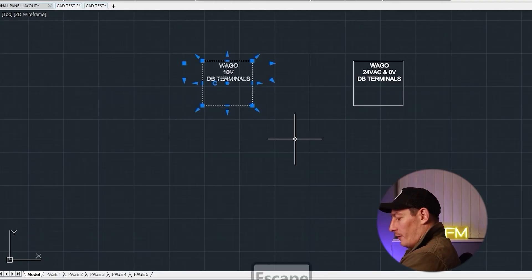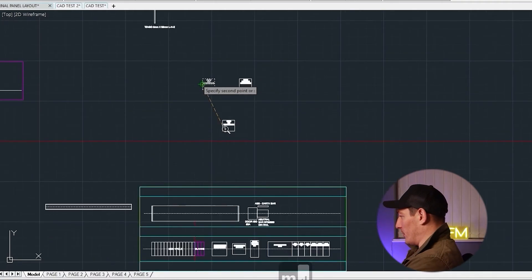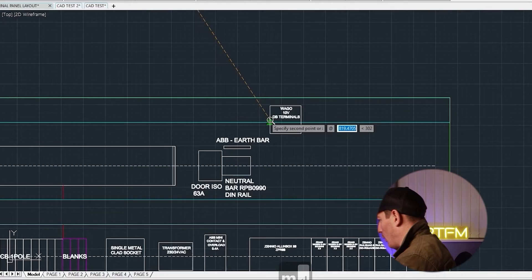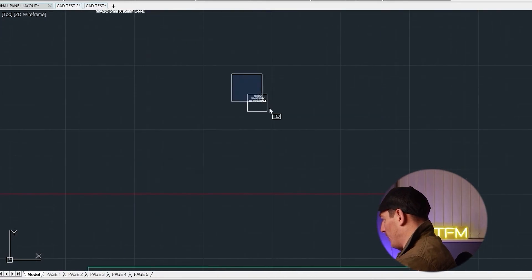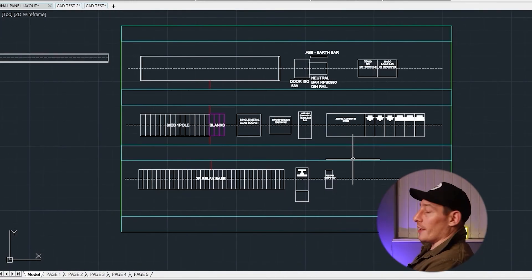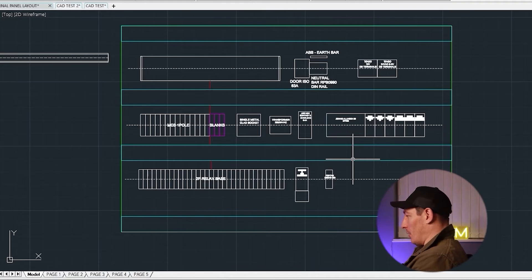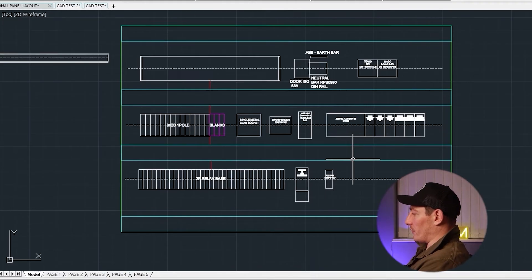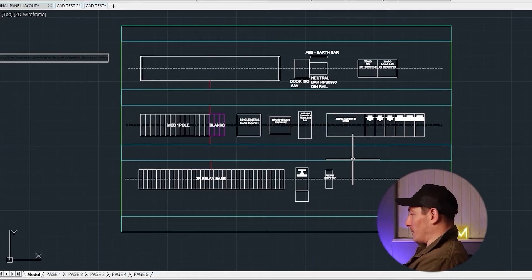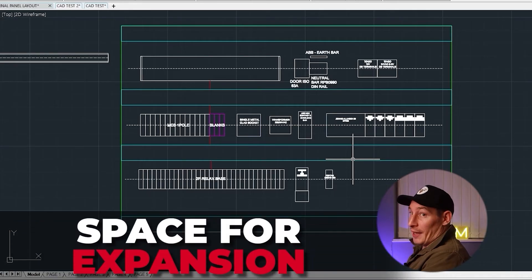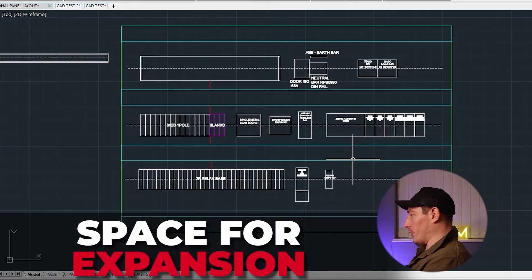Okay, and then the final bits guys are just some Wago distribution blocks. Let's put these there for now. But yeah, as you can see I think that size panel is a good size for all of those components - they're not all cramped in, there's not loads of space, but there's some space for expansion which we definitely want to include. So yeah, I think that enclosure size is good as a starting point.